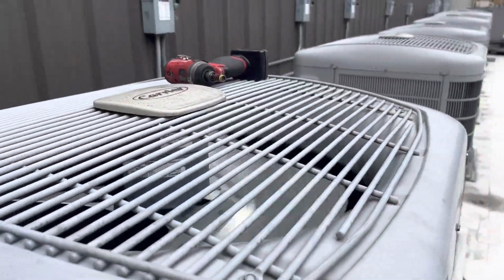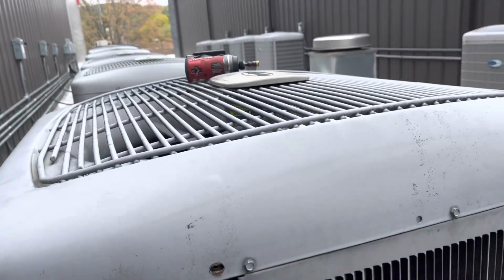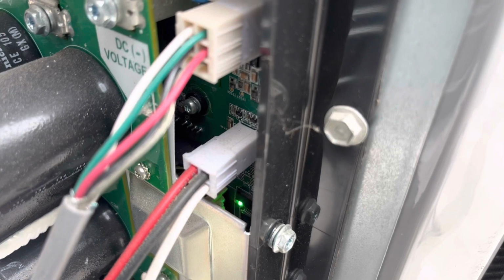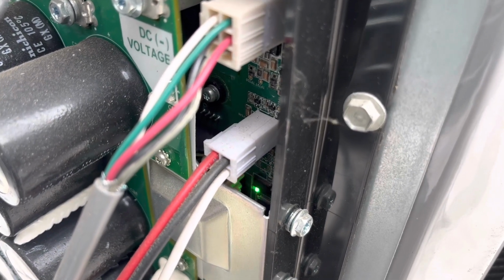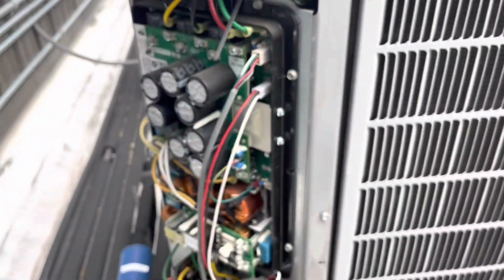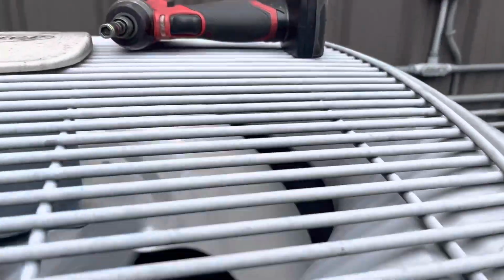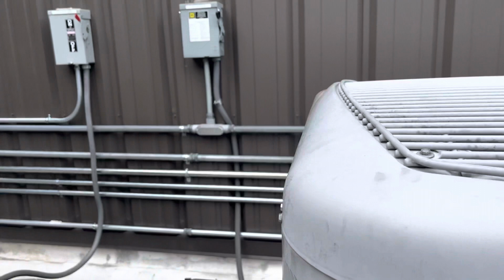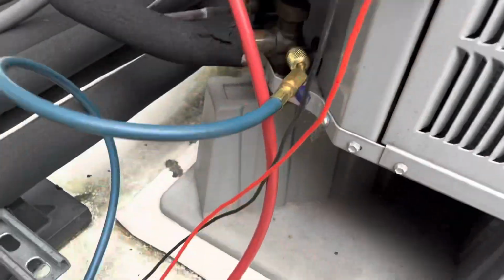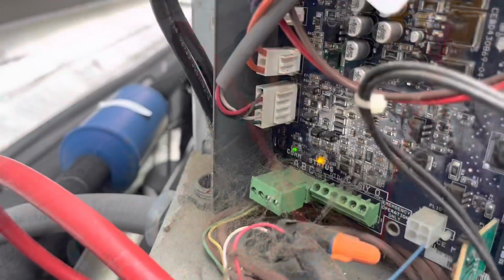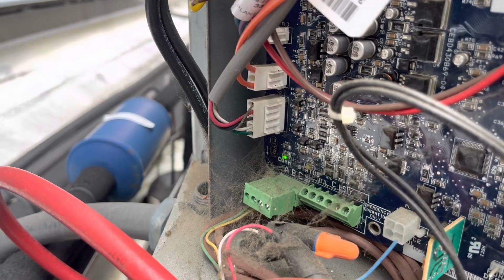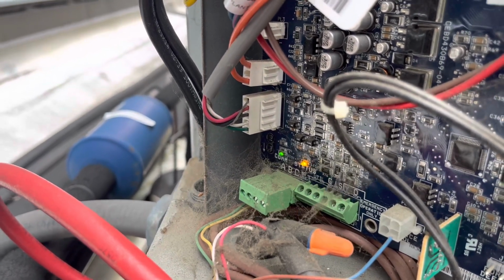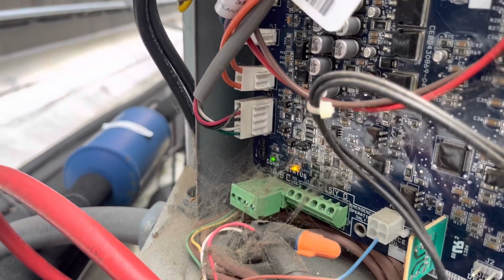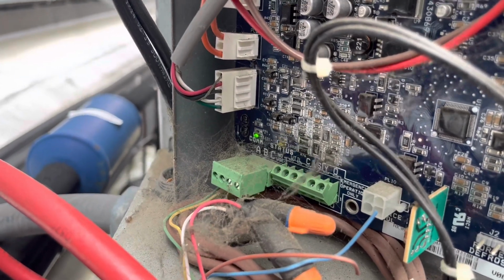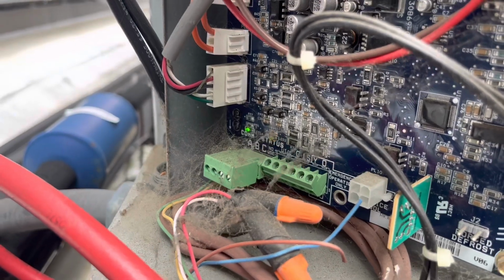Spinning now with the compressor unplugged. And it should throw a code. We'll let it do its thing, go through a cycle. As you can see, it's not, the compressor's unplugged. 9 blinks on my amber. One, two, three, four, five, six, seven, eight, nine, and then fast blinks. One, two, three, four, five, six, seven. So 9 and 7.